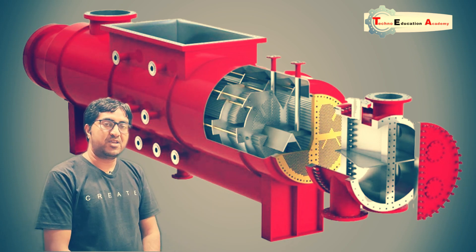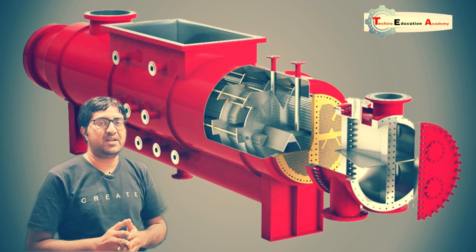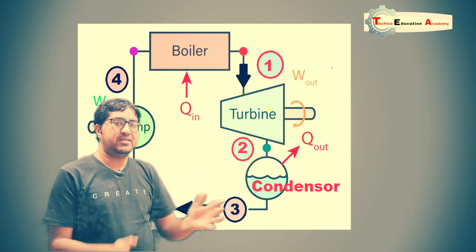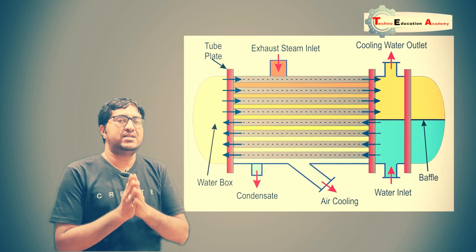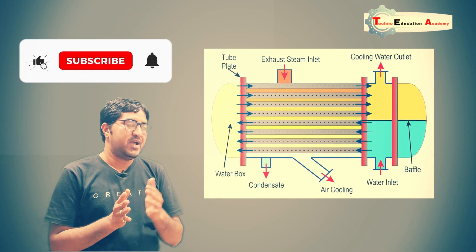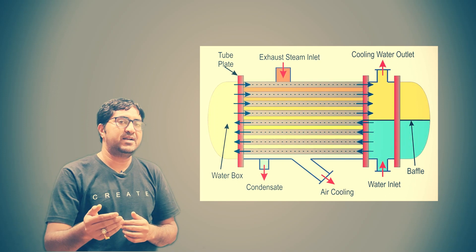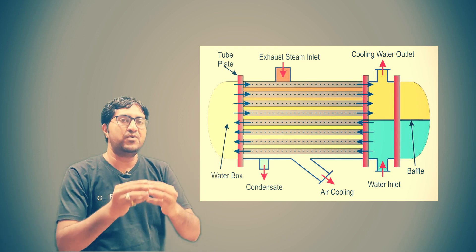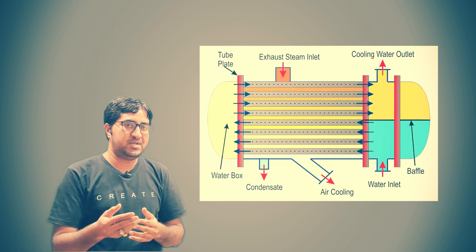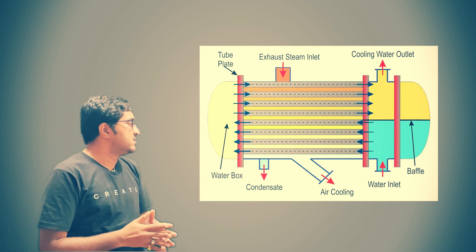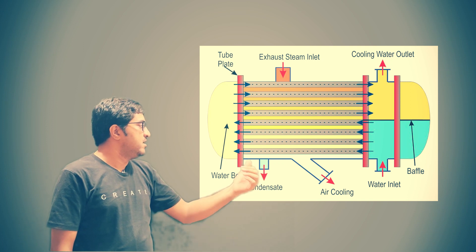The condenser is connected with a vacuum pump, or in some cases a vacuum system when large vacuum is required. The condenser is a type of heat exchanger where heat is exchanged between a cold fluid and a hot fluid — steam as the hot fluid and cold water or sea water as the cold fluid. This is called a surface condenser because only the surface area of the tubes is used to transfer heat, with no physical contact between the two fluids.